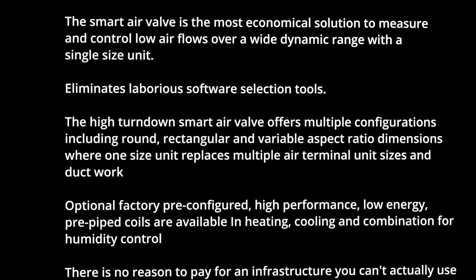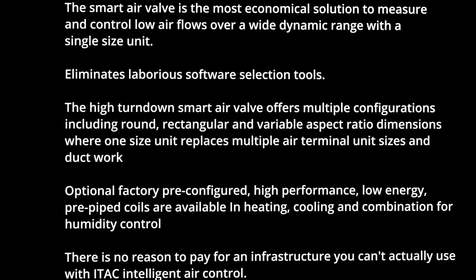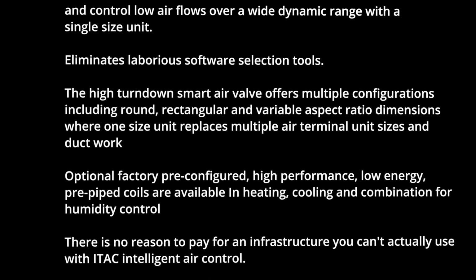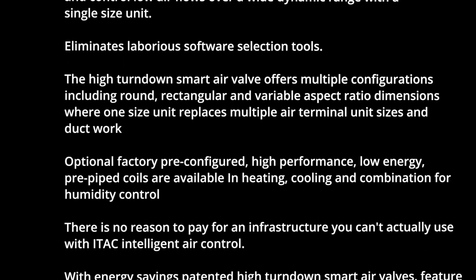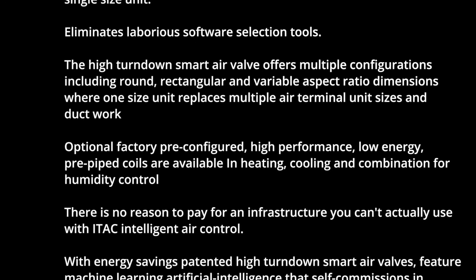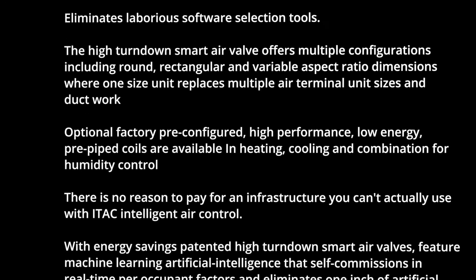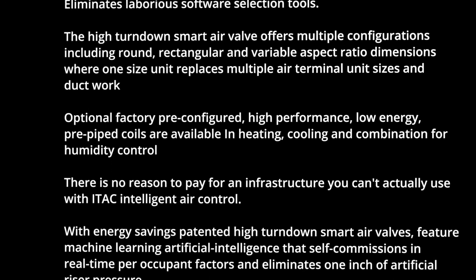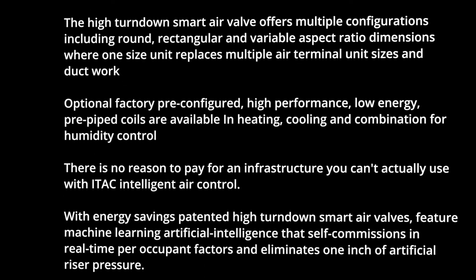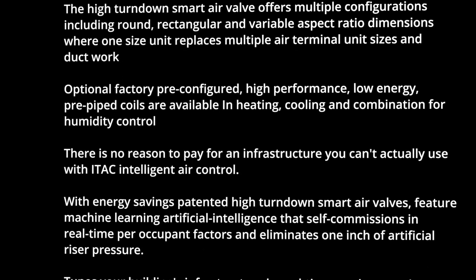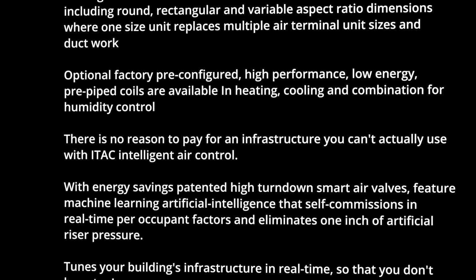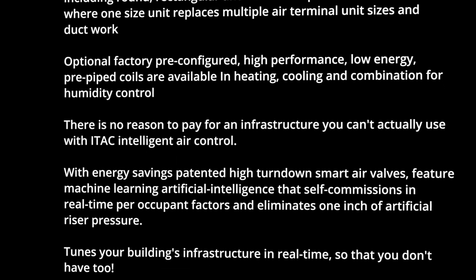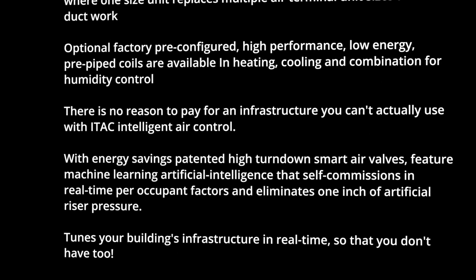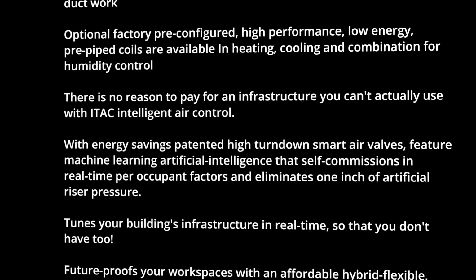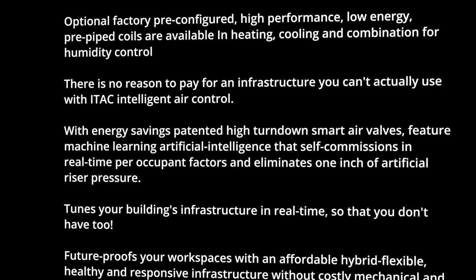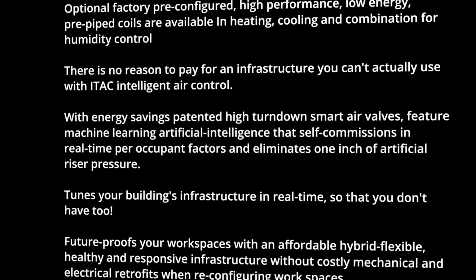Eliminates laborious software selection tools. The high turndown Smart Air Valve offers multiple configurations, including round, rectangular, and variable aspect ratio dimensions, where one size unit replaces multiple air terminal unit sizes and ductwork. Optional factory pre-configured, high-performance, low-energy, pre-piped coils are available in heating, cooling, and combination for humidity control. There is no reason to pay for an infrastructure you can't actually use with ITAC Intelligent Air Control.